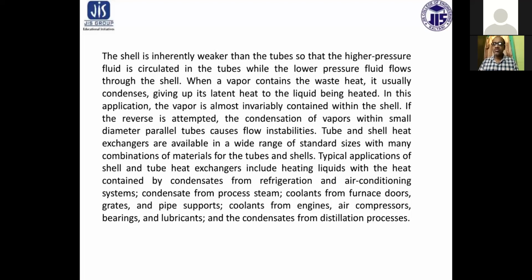So instead of flowing high temperature vapor inside the tubes, which would restrict the flow of liquid due to the condensation process, it is kept in the shell. Tube and shell heat exchangers are available in a wide range of standard sizes with many combinations of materials for the tubes and shell.